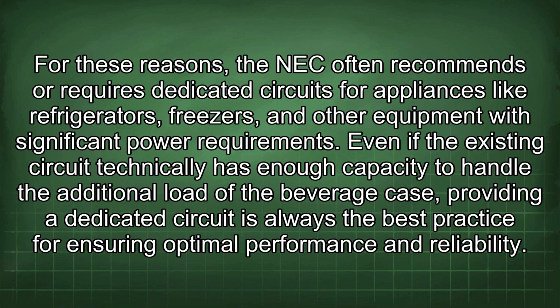spoil. For these reasons, the NEC often recommends or requires dedicated circuits for appliances like refrigerators, freezers, and other equipment with significant power requirements. Even if the existing circuit technically has enough capacity to handle the additional load of the beverage case, providing a dedicated circuit is always the best practice for ensuring optimal performance and reliability.